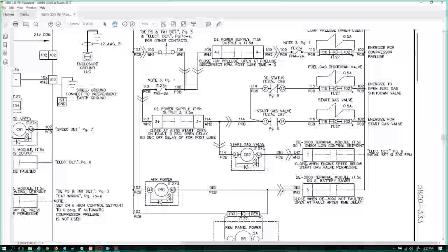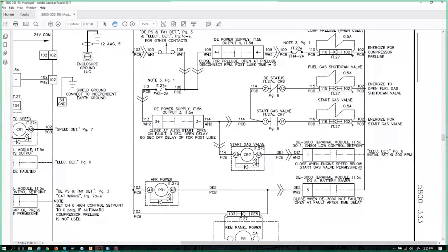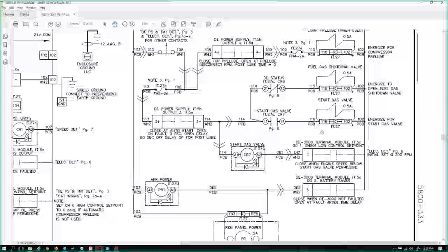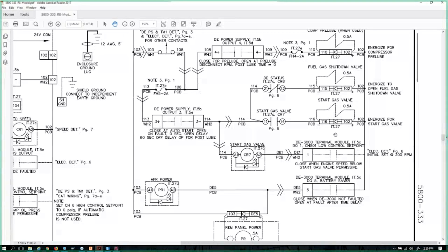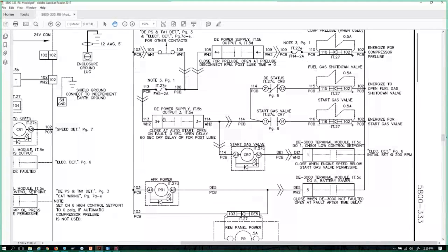So what we're saying here is as soon as the RPM becomes greater than that 500 value that we just saw from the software, this will de-energize and the contact will go open. We'll de-energize this relay and this contact will throw open, and we will de-energize our start gas valve and it can return to the closed state. So the reason I like to show you that is it utilizes two things. It utilizes, one, the low control set point, something that I hadn't shown you in the software yet. But it also utilizes some of the strategy that I said we could do with output module 3 on the OEM startup sequencing. A lot of people use start gas pressure to do two things: control a prelube cycle as well as supply for their starters. So the second note on here is it says open on fault 0 seconds.